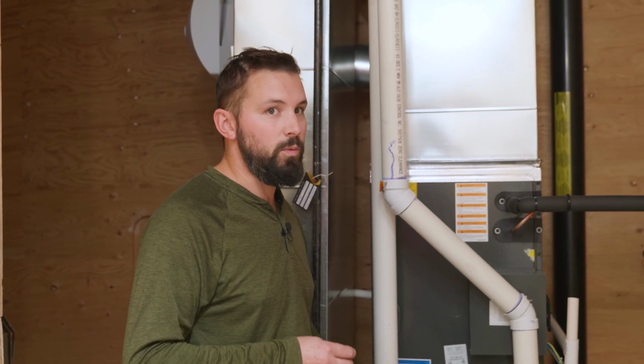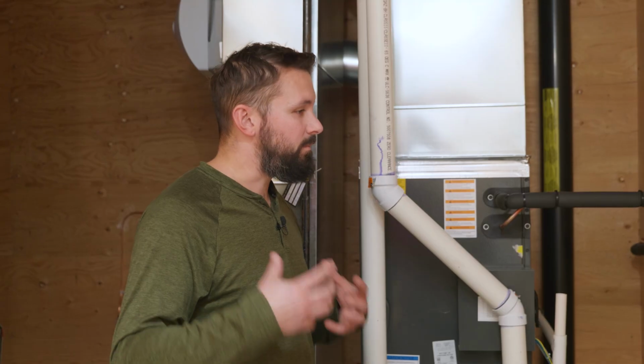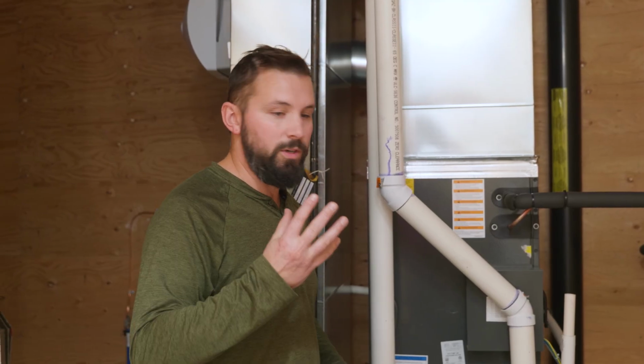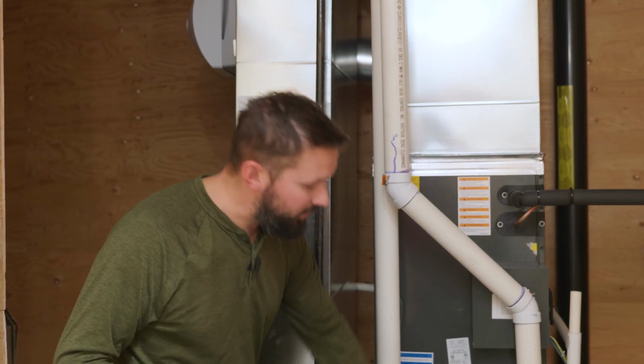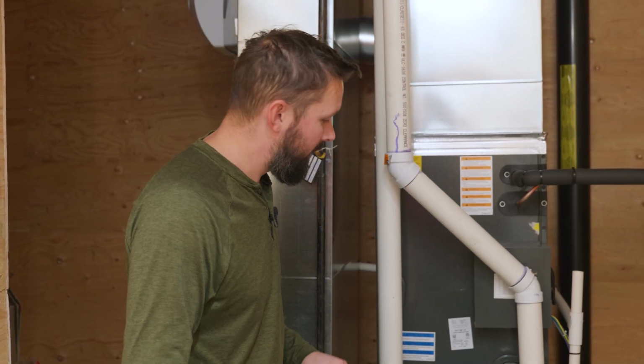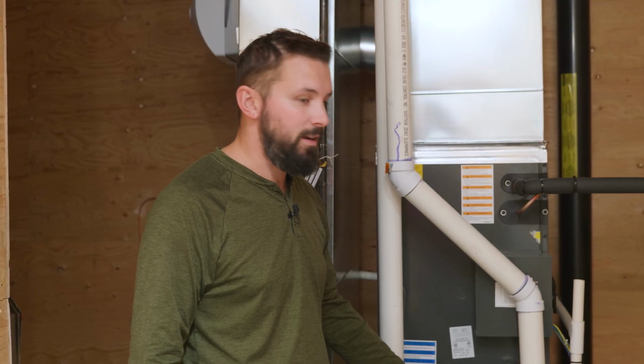Any air handler powering a modern house is going to have a constant draw. It's going to be running that fan 24 hours a day, 7 days a week, if we don't have a dedicated ducted system for our ventilation. Most homes are going to use the HRV or the ERV, put it to the return air plenum for the furnace, and then use this to circulate it around the house. That fan motor is a constant draw 24 hours a day, like I said.